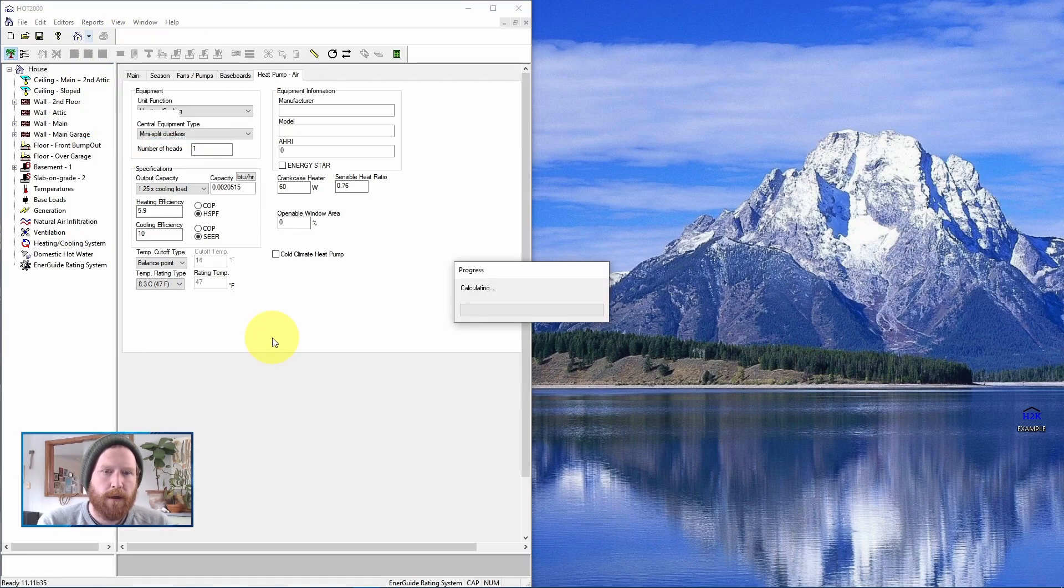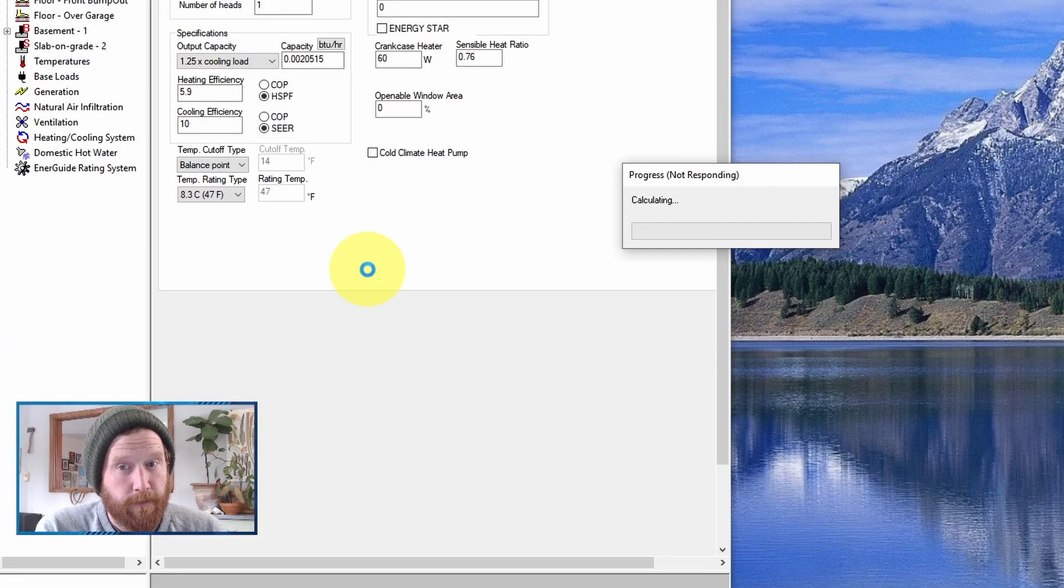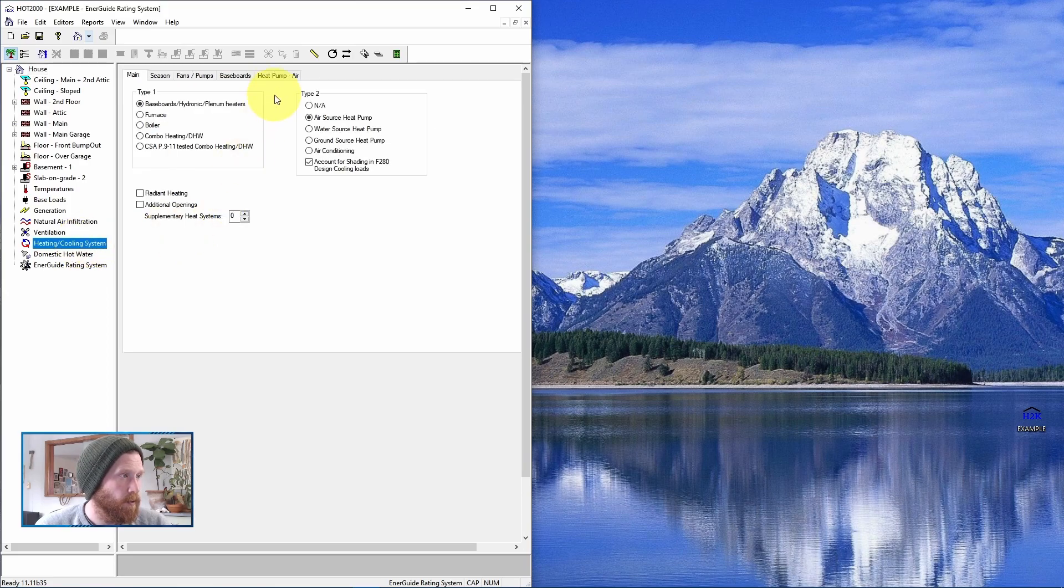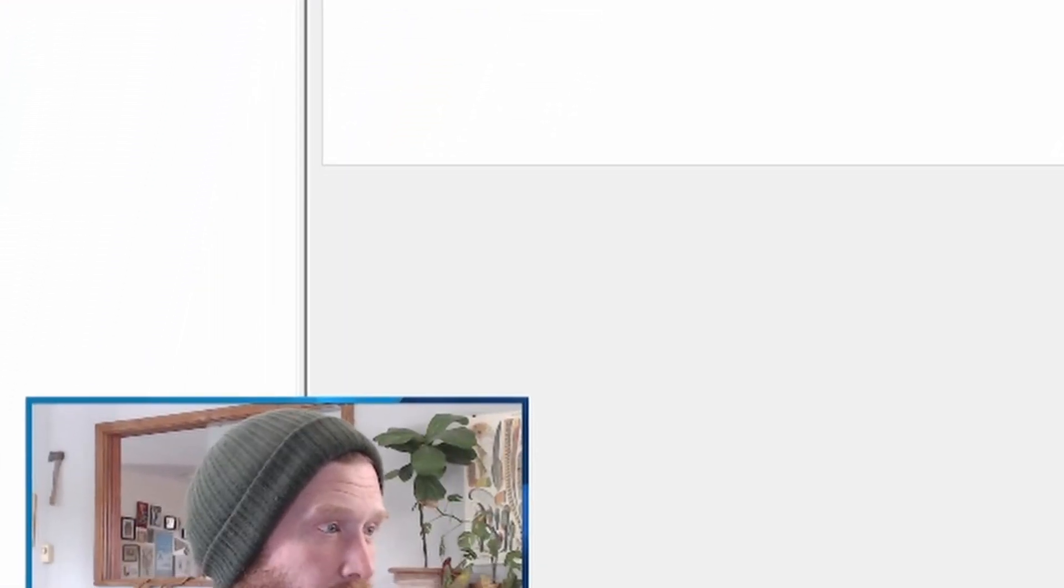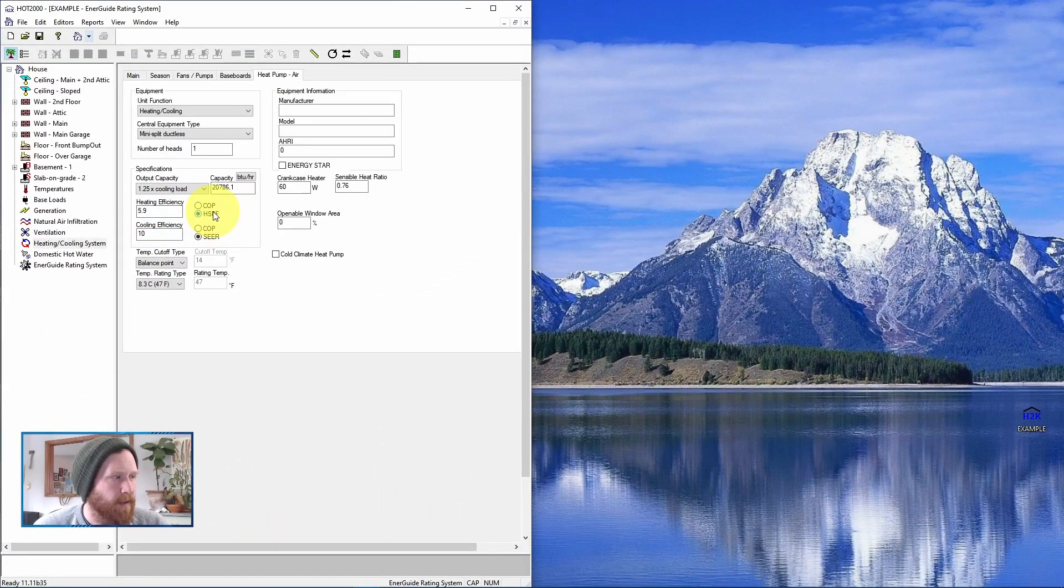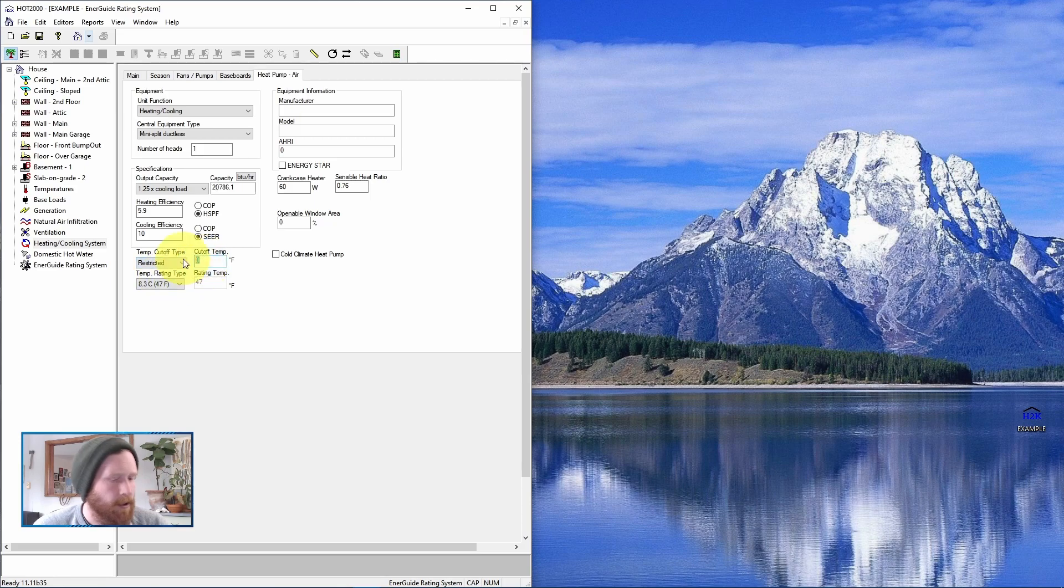Depending on your computer, this may be faster or slower. For some reason, mine seems to be really slow. Still waiting. Okay. And then once this is calculated, we can just close this. But what that has done, if we go back to heating and cooling, we go to heat pump, it has set our capacity for us. So if the capacity is lower than 24,000 BTUs, which it is in this case, we would just leave it. If it's higher than 24,000 BTUs, then you drop it down to 24,000 BTUs. And then we just leave the heating efficiency at 5.9, cooling efficiency at 10. And I'm going to switch this to restricted at 14 degrees. And then we're done. So that's how you enter a default heat pump.